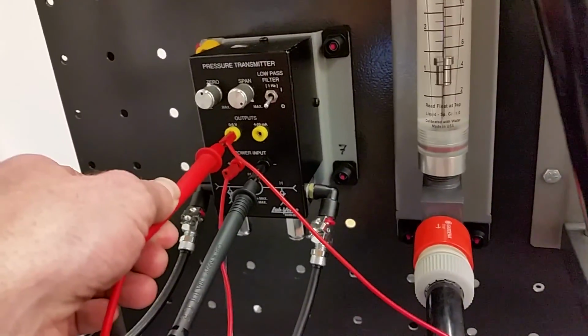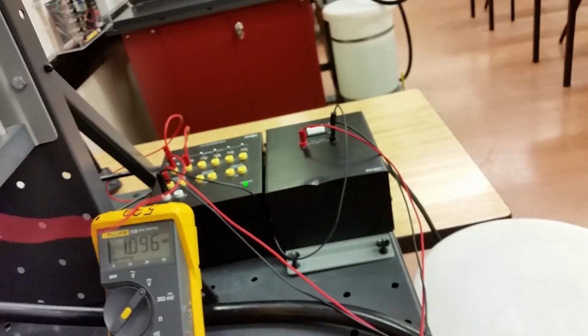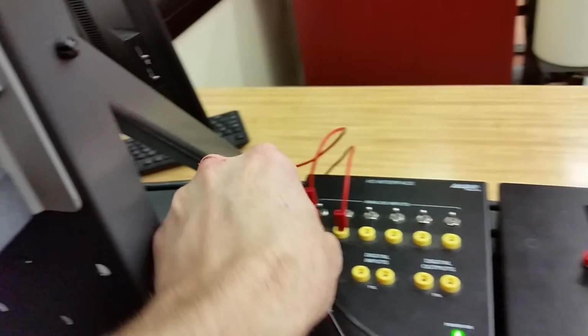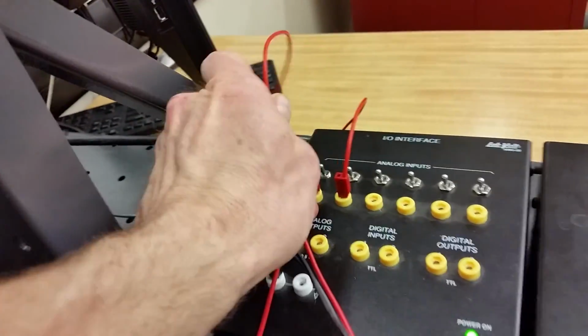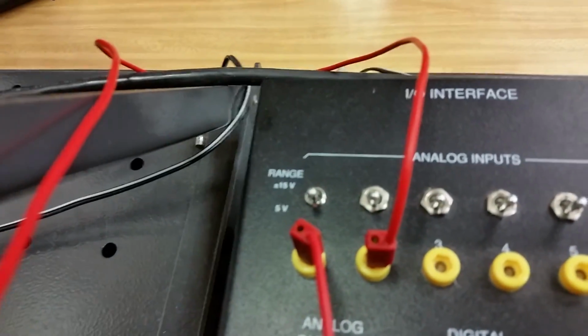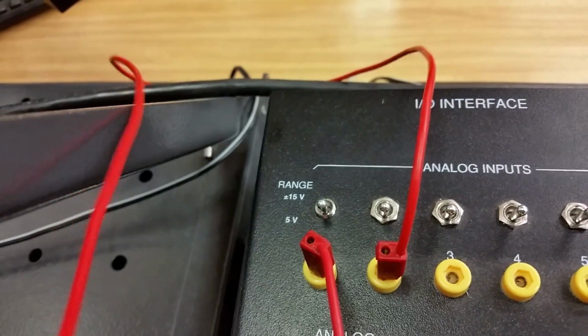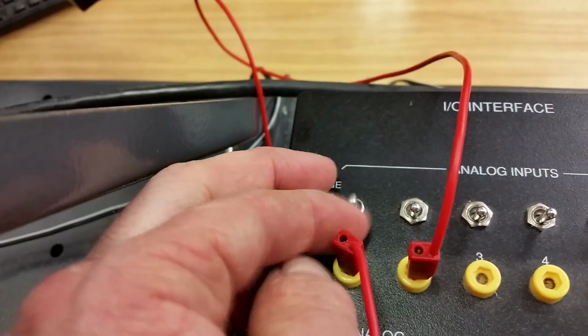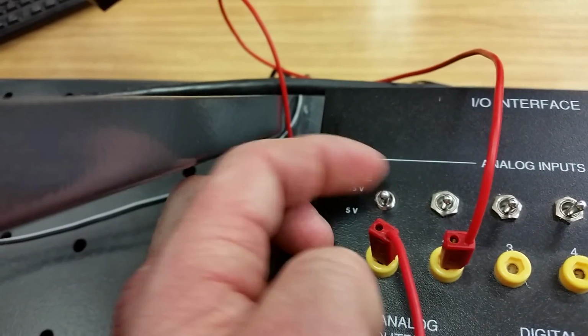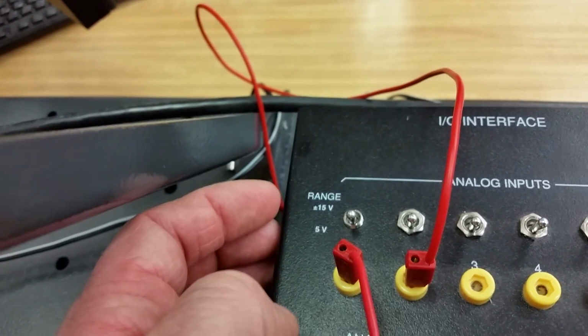So how do we do that? Well, this is our reference for that voltage with the meter. What we're going to do is take a long lead and bring that over to this point right here. We're going to bring it into the analog inputs. Make sure that the dip switch is at 5 volts. When everybody's bored, they start flicking switches. Make sure it's referencing 0 to 5 volts.